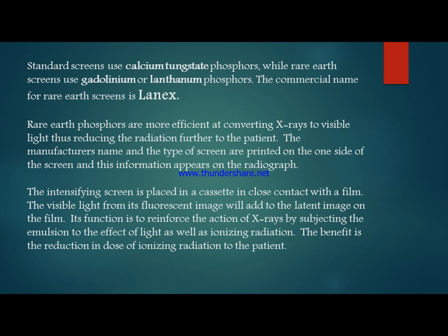Lanthanum phosphors are commercially named for rare earth screens as Lanex. Rare earth phosphors are most efficient at converting X-rays to visible light. Thus, they reduce the radiation dose to the patient further. The manufacturer name and the type of screen are printed on one side of the screen, and the information appears on the radiograph.